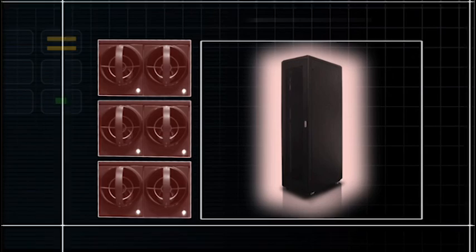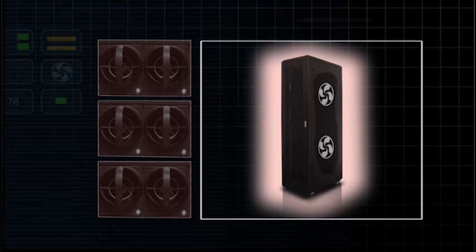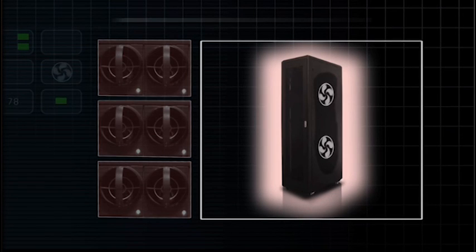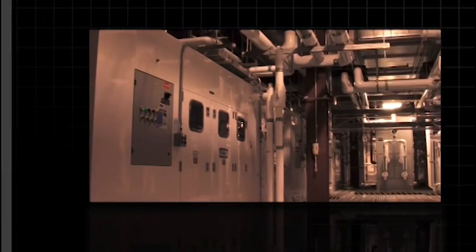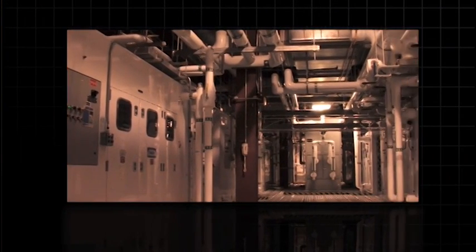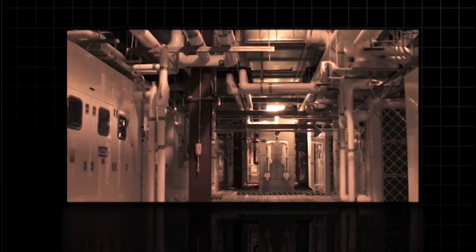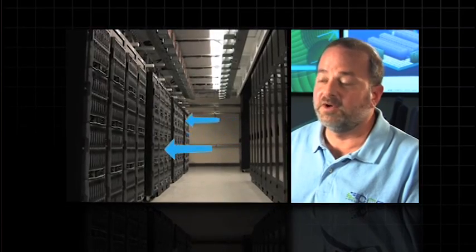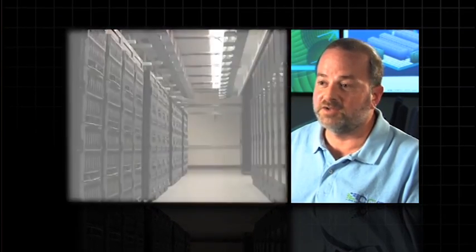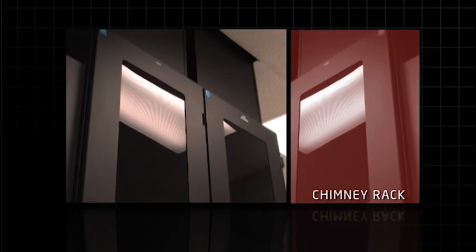By putting a chimney on the back of the rack and then cleaning up the airflow obstructions in the rack, you're not relying on those little fans in the cabinet anymore, but you're relying on the big air handling units to move that air through. And all that is going directly through those racks in a very controlled fashion, and that's because of the chimney rack.